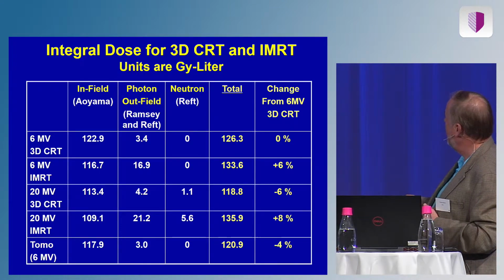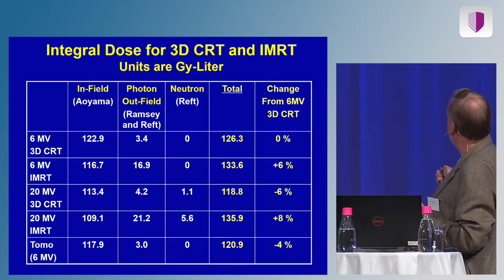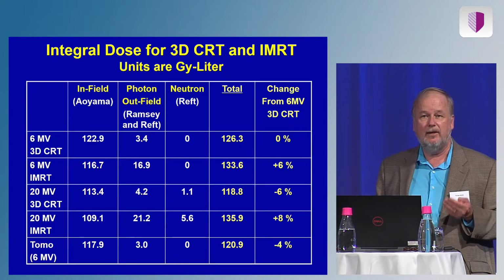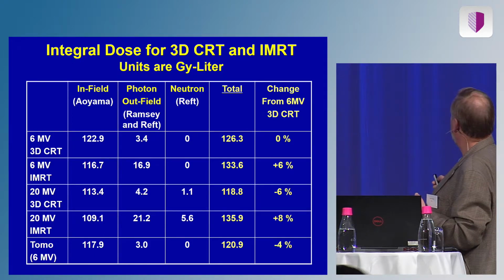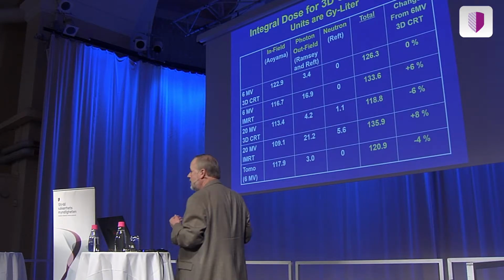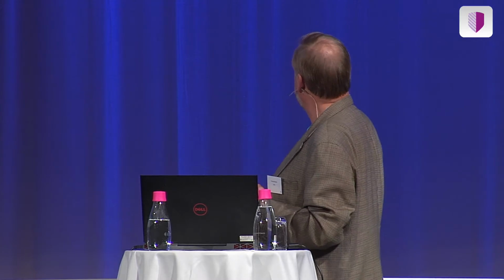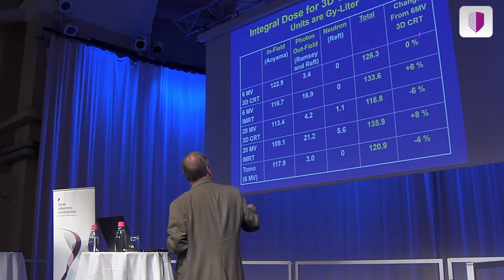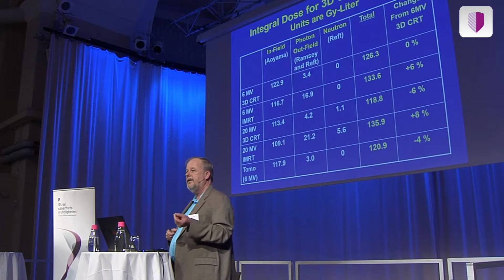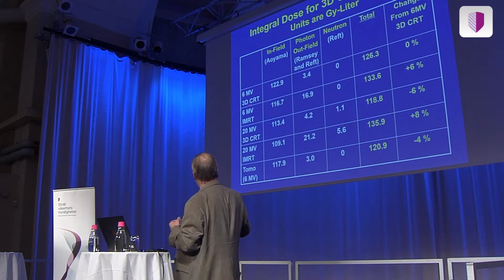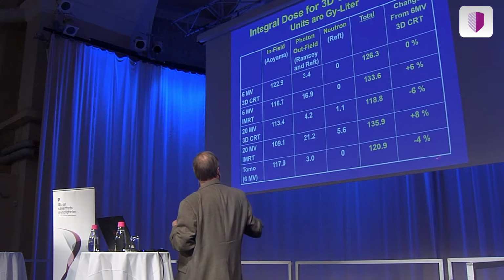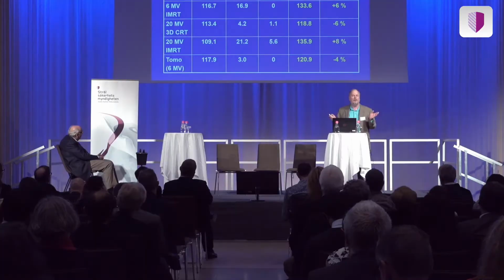But the 20 MV IMRT was greater than the 6 MV 3D conformal. And why is that? Well, it was because of the neutron component, because this beam produces neutrons, whereas 6 MV doesn't. And then if you add the extra shielding, then you can be somewhat better than the 6 MV 3D conformal. But really, another story here is that it only varies by, at most, 8%, okay, whatever you do. So integral dose really is almost invariant.